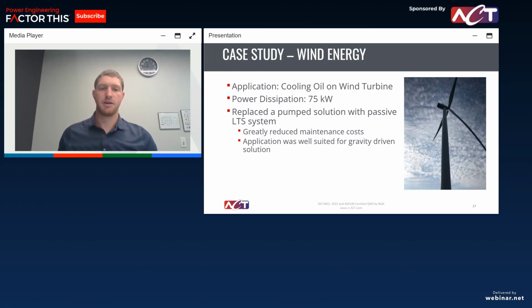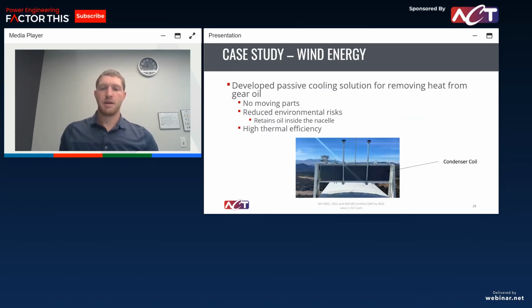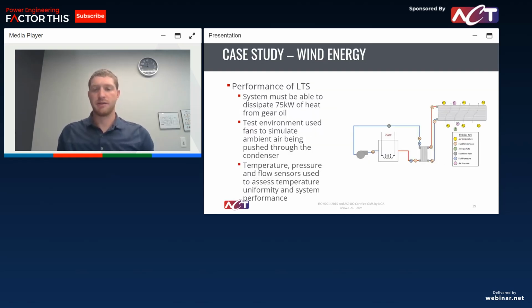That greatly reduced their maintenance costs, and as you can imagine, maintenance up in a wind turbine is not inexpensive. And due to the height of the turbine, loop thermosyphon was a very useful technology because of the gravity. You have a lot of height difference to work with there. As we talked about, no moving parts means greater reliability, less maintenance, and high thermal efficiency. You can see this is our condenser coil on top of the wind turbine, and then it travels down to where it gets the heat from the gear shaft.